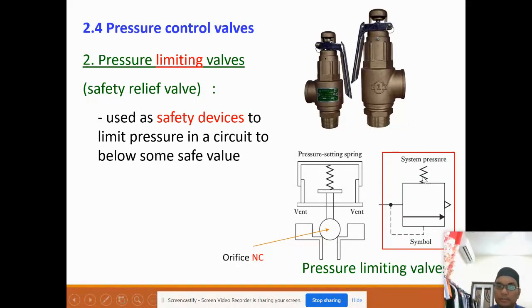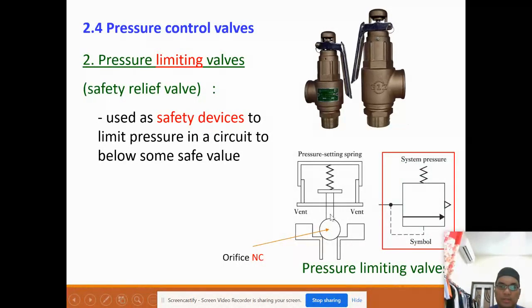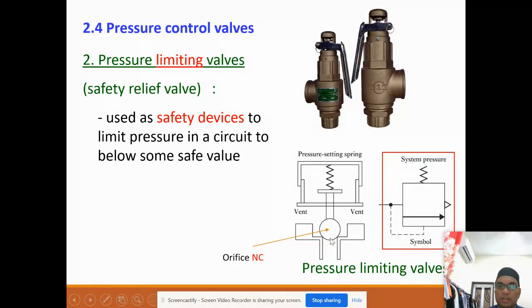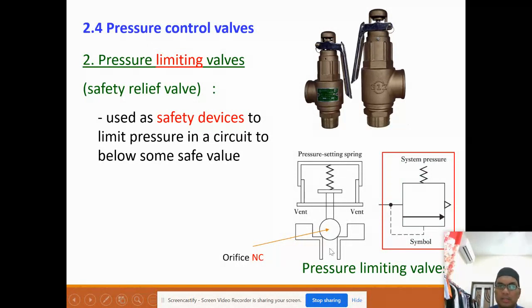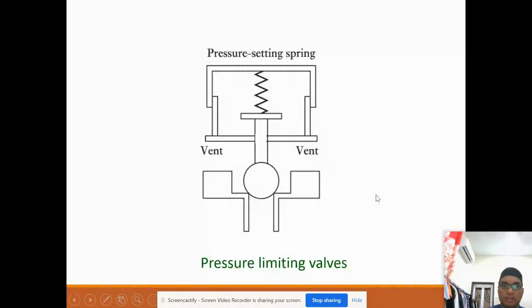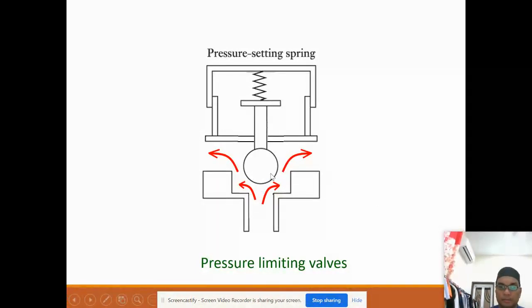This device is basically used as a safety device to limit the pressure in the circuit to below a safe value. This is the symbol — it has the inlet here, and when activated, it connects to release the pressure. It is controlled by a spring and is normally closed. In an emergency or safety condition, when there is sufficient force, the spring will open and release the air to the atmosphere, as shown in the animation.